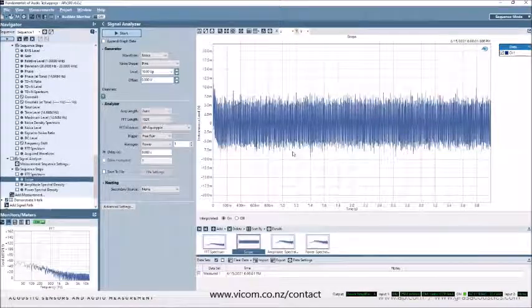Thank you, Dan. Another question here. Why use a sweep signal instead of each sine frequency to perform THD and HOHD measurements? And what is the advantage of a sweep signal? So I assume the question relates to using a log chirp, and the answer is very simple. The answer is time.